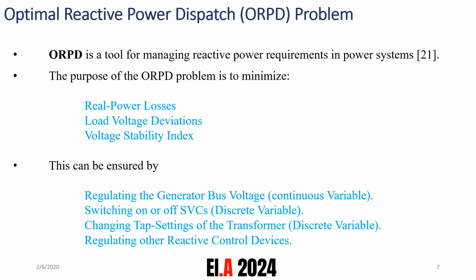Optimal reactive power dispatch is a tool for managing reactive power requirements in a power system. The purpose of the optimal reactive power dispatch problem is to minimize the real power losses, load voltage deviation, and voltage stability index. This can be ensured by regulating the generator bus voltage, which is a continuous variable, and switching SVCs on or off, which is a discrete variable. We can also ensure it by changing the tap setting of the transformer and regulating other reactive control devices.